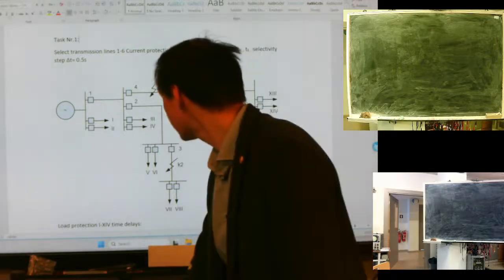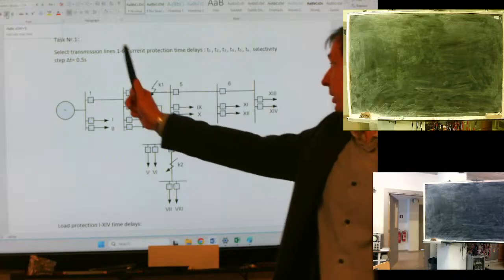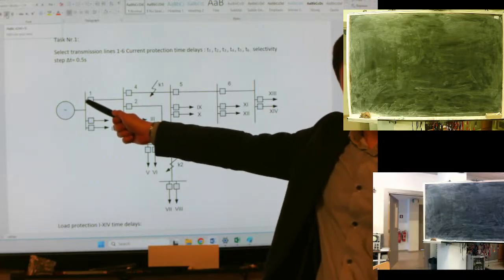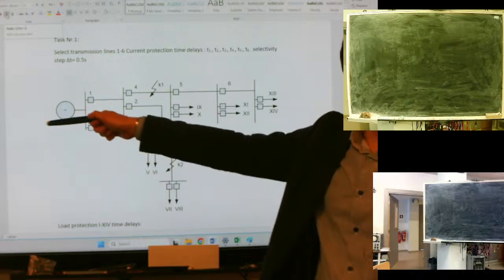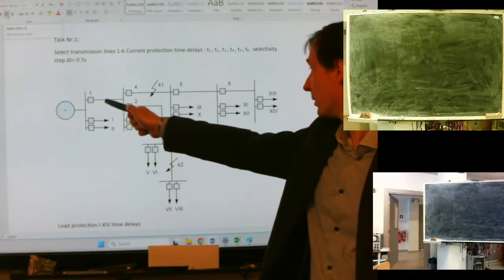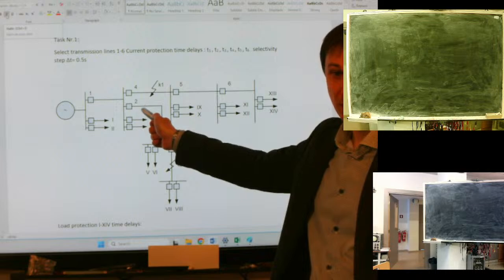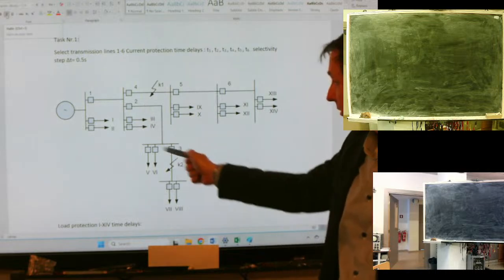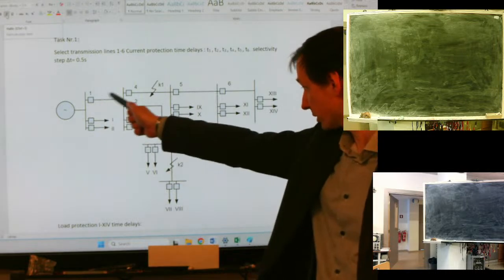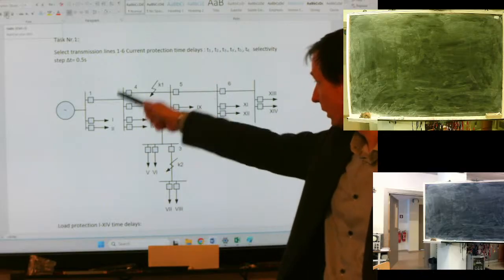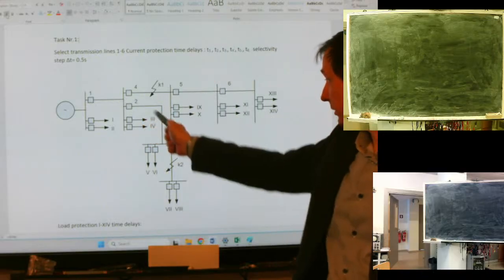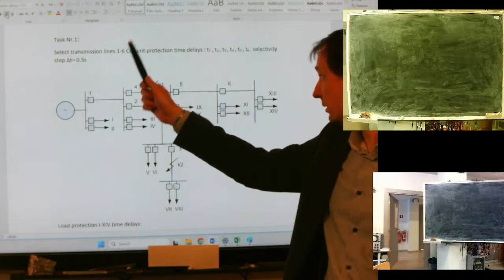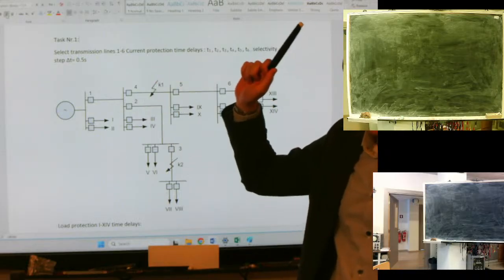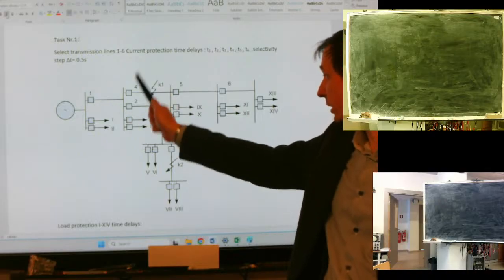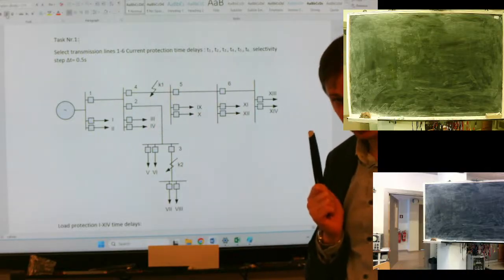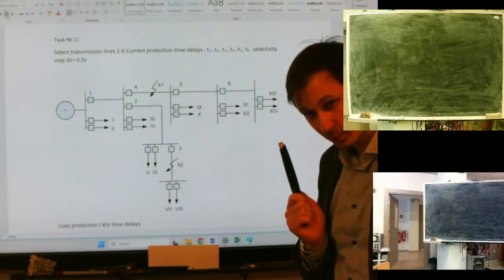Because in this case, current protection 1, because they are in series, and we understand the fault current is in line 2, in line 1, and in line 3 as well, because this is our direction from the power source. So we have the fault current. And in this case, do we want current protection 1 and current protection 2 to detect this fault as well?